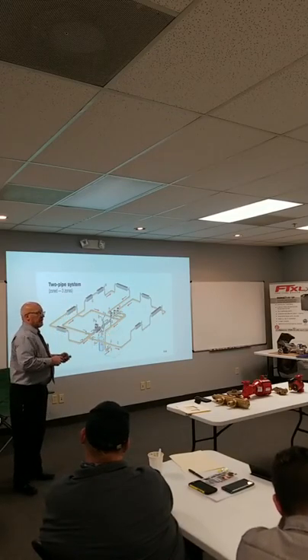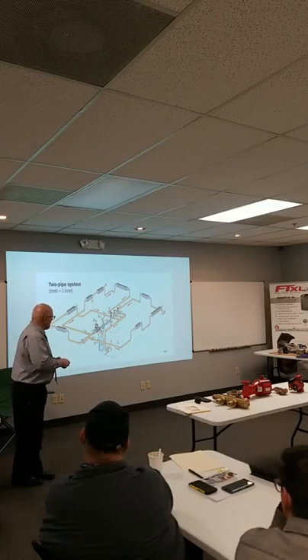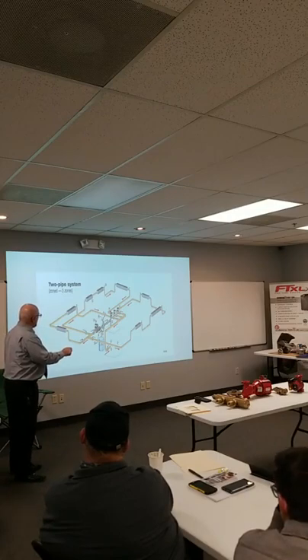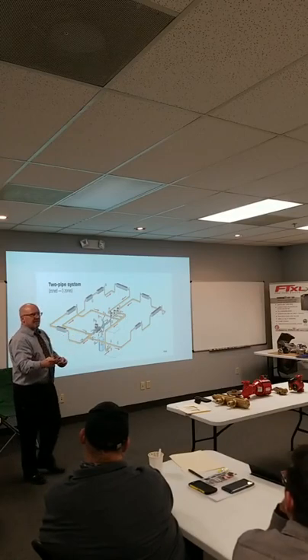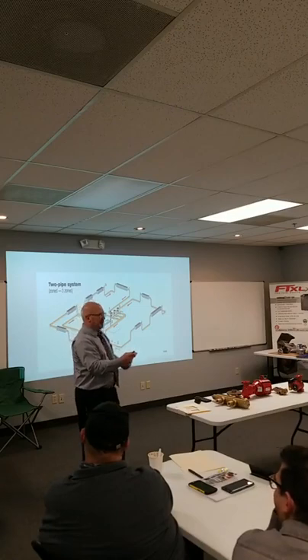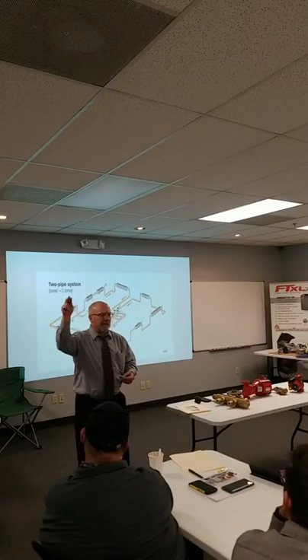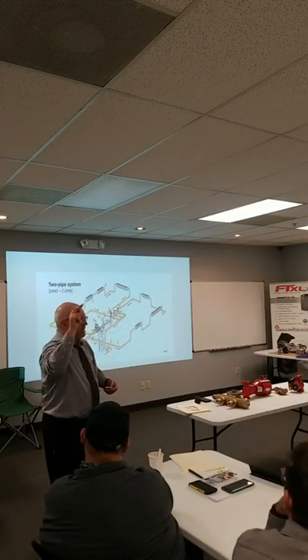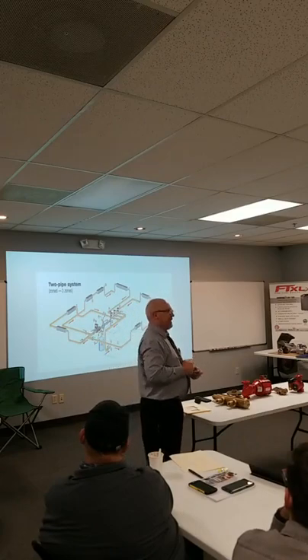Pump away from the point of no pressure change. You're always going to be better off. Because of the pump differential, if I'm pumping into the boiler, and the expansion tank's here, my only increase in pressure that pump is producing is from where that pump is on the return, pumping into this point. The rest of the differential the pump is producing is a negative pressure. So on the third floor, that automatic air vent you put on, because you're constantly getting air on the third floor, that hissing you hear may not be venting air, it might be sucking air in.